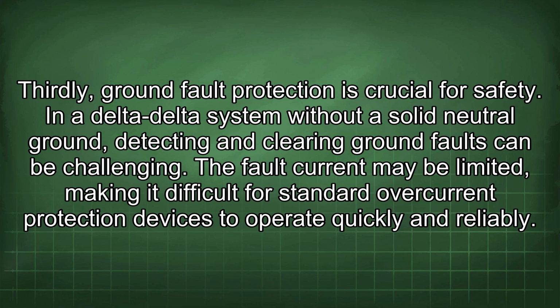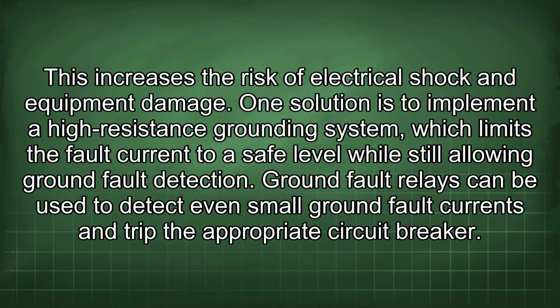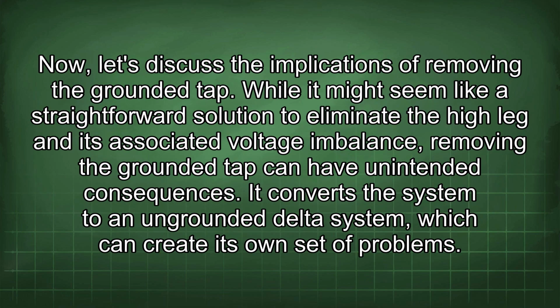Thirdly, ground fault protection is crucial for safety. In a delta-delta system without a solid neutral ground, detecting and clearing ground faults can be challenging. The fault current may be limited, making it difficult for standard overcurrent protection devices to operate quickly and reliably. This increases the risk of electrical shock and equipment damage. One solution is to implement a high-resistance grounding system, which limits the fault current to a safe level while still allowing ground fault detection. Ground fault relays can be used to detect even small ground fault currents and trip the appropriate circuit breaker. Now let's discuss the implications of removing the grounded tap.